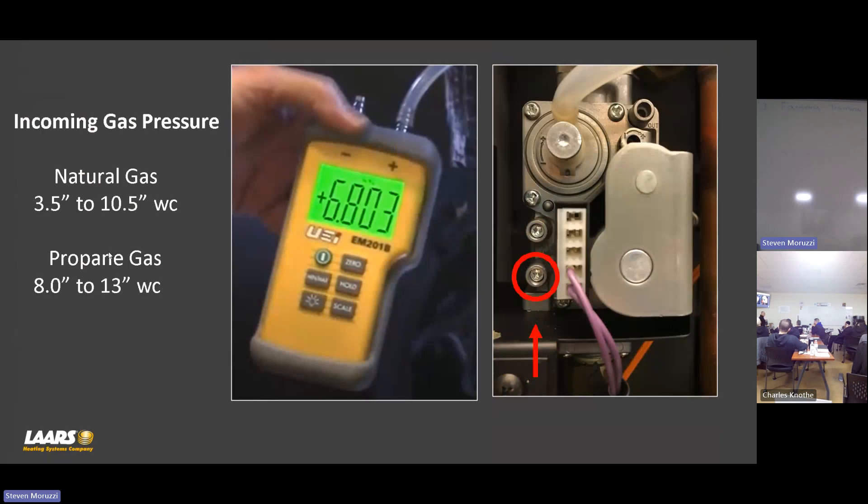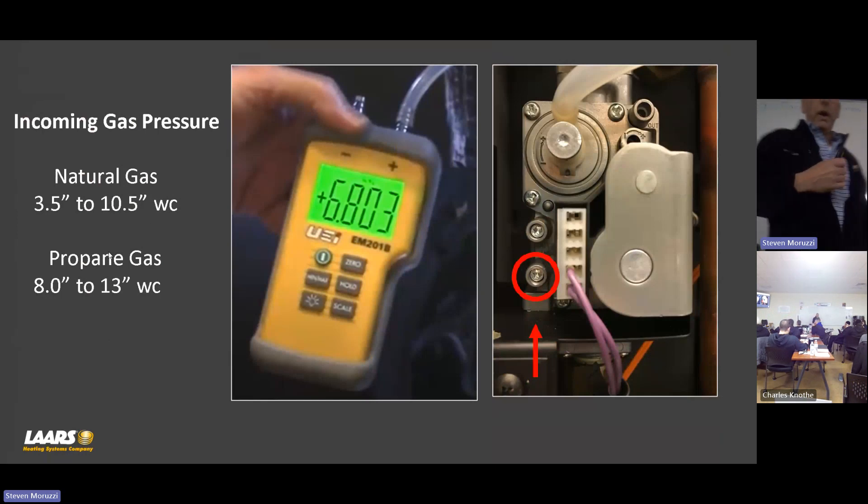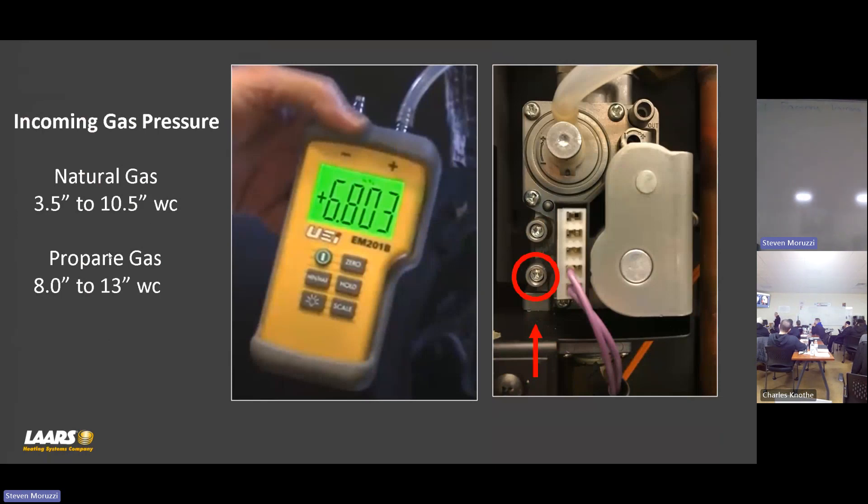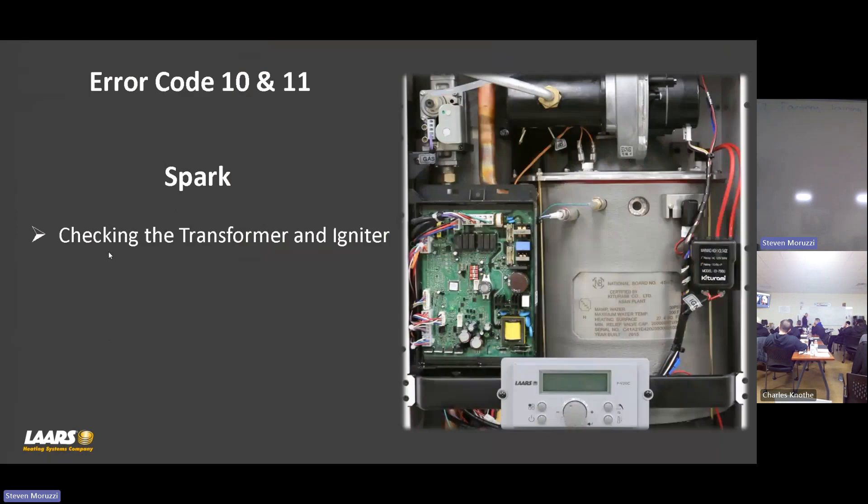One full inch. So in this example, put a manometer on, we're reading 6.8. We want to run all the appliances. What is that pressure drop? We do not want to see greater than a one inch pressure drop. That means I don't want to be any lower in this example than 5.8.